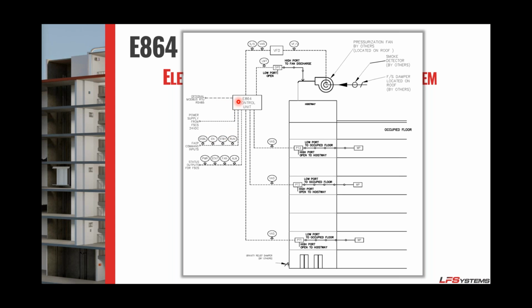Once we get our start command, we send a signal to start the VFD, which then starts the fan. We verify through a pressure switch that the fan is operating. Then we start to modulate based on the 3 sensors. We can modulate based off the highest, the lowest, or the average. On stairwells, we primarily focus on the low side. On elevators, we use more of an average because of the piston effect. We want to make sure that quick spikes are not taking over and changing things too quickly. We can have a relief damper at the base, which helps with some of that excess pressure as well.